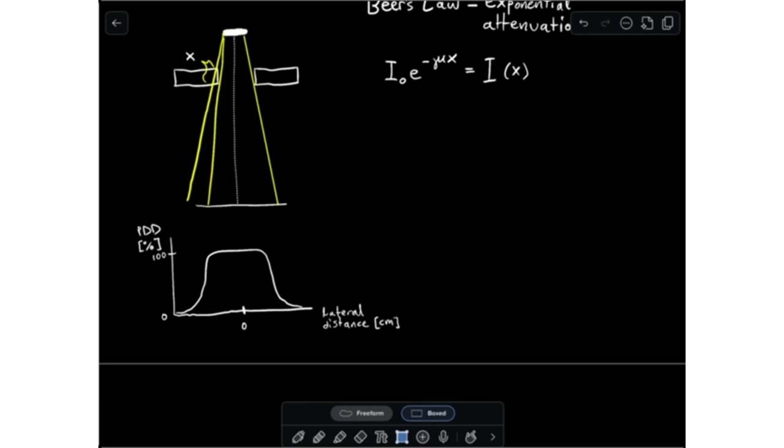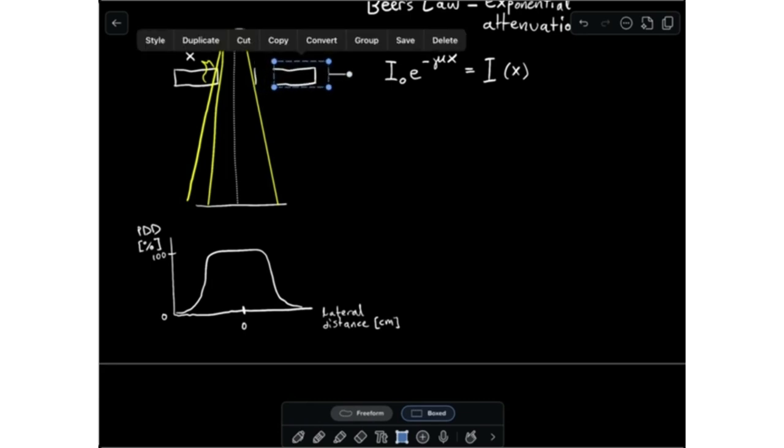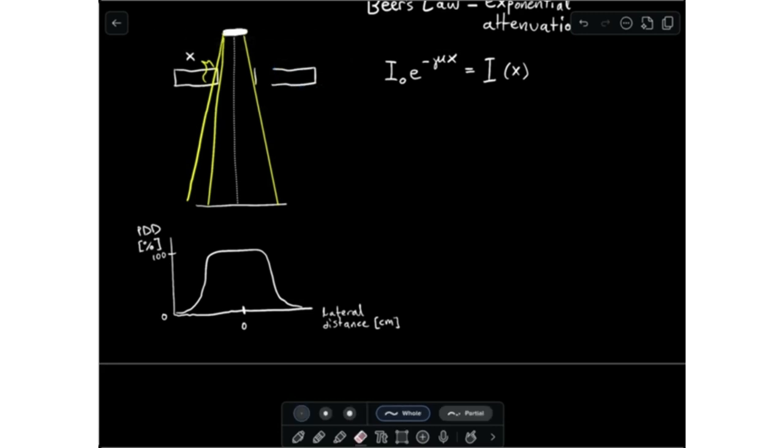And so there have been some techniques developed in collimator design to mitigate the effect this has on the dose uniformity of the field, including the machining of collimator blocks so that they have this angled edge, and this way there's a much more abrupt change in intensity between the unattenuated inner field edge and the part that just begins to be attenuated by the suddenly large thickness farther out.